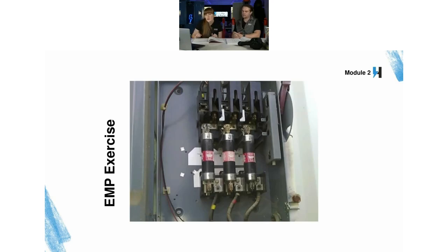I believe that's an FRS-R fuse. Yeah. And this is a low voltage application, so we're good to go. FRS-Rs are rated up to 600 volts, and assuming this is a 480 volt system, it should be rated for this system. Yep. So that's an example of a quick visual inspection there.